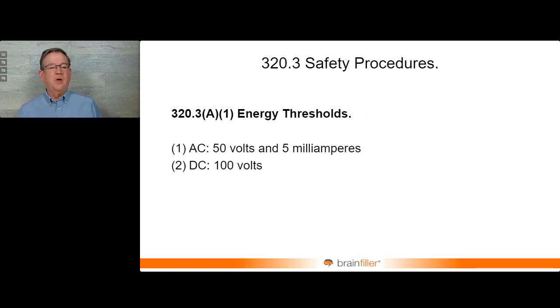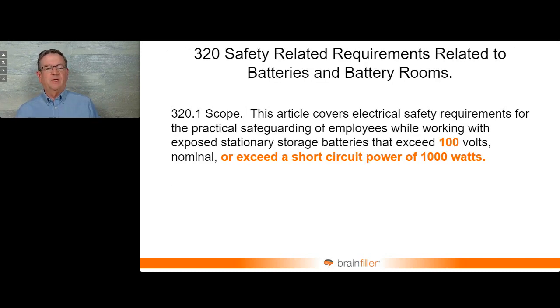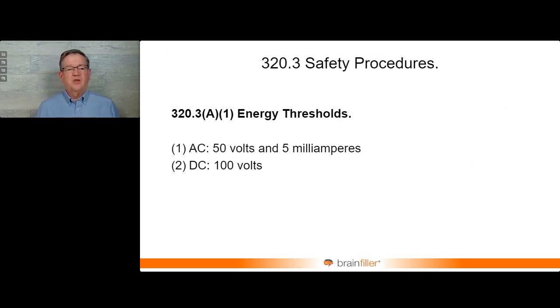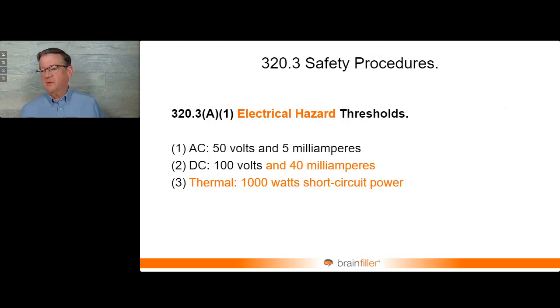And like in 320, AC thresholds are 50 volts, just like we have in Chapter 1, 5 milliamps, which is actually where ground fault circuit interrupters begin to trip. And then we had DC in there, 100 volts. So the initial problem was this is what we had, 100 volts. But up here, we had 50 volts. So we needed to make a change. The change was made. And then also, a threshold of current and a threshold of short circuit power was added here as well.